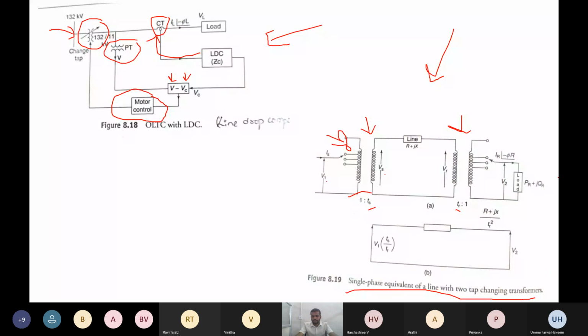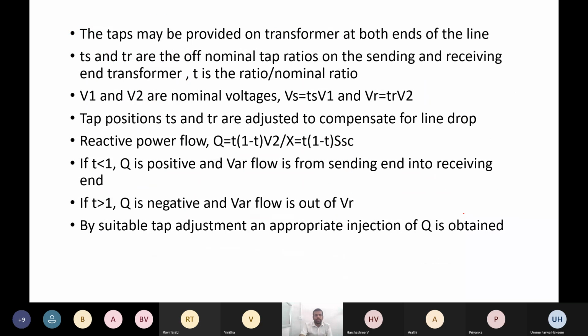So Vs is equal to Ts into V1, and Vr is equal to Tr into V2. So Ts and Tr are our off nominal tap changing ratios. And here the tap positions Ts and Tr are adjusted to compensate for line drop. The line drop is nothing but voltage drop, the V1 voltage drop and V2 voltage drop. So depending upon the voltage drop, the Ts and Tr will be adjusted.